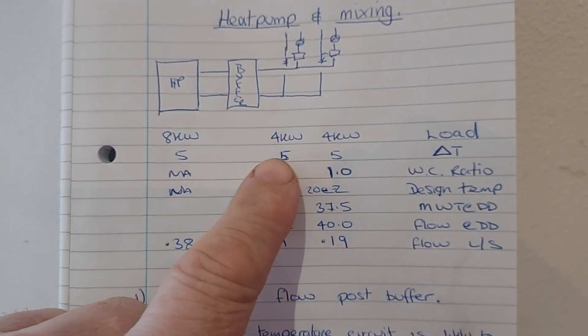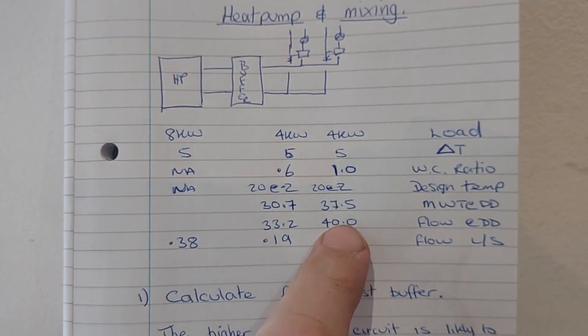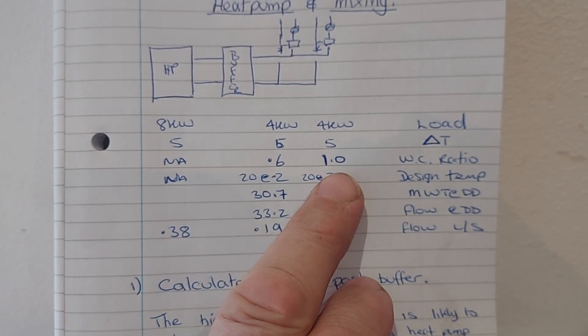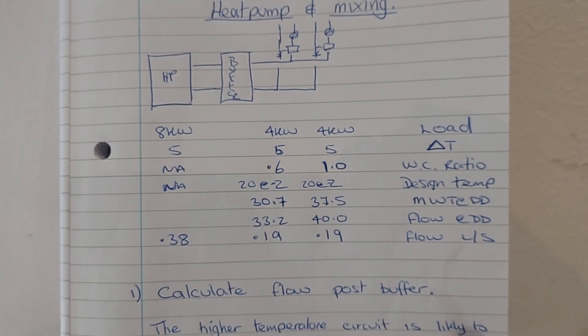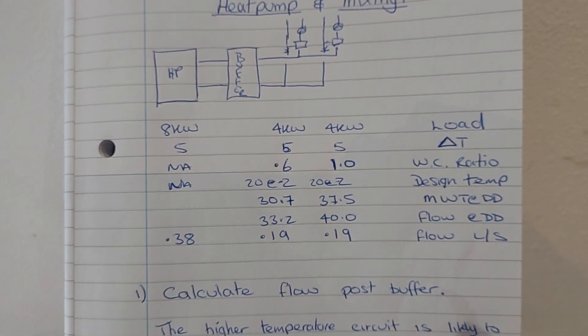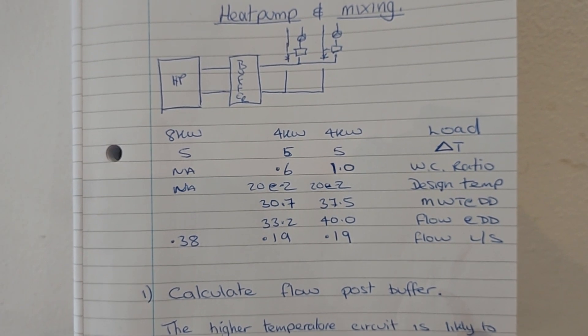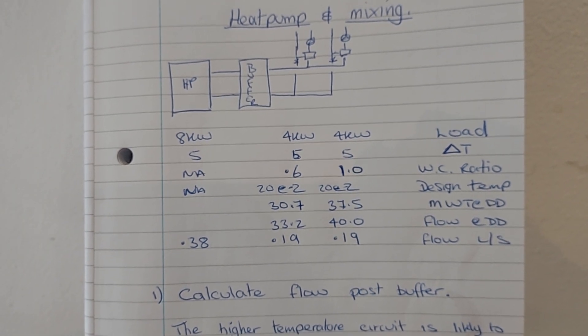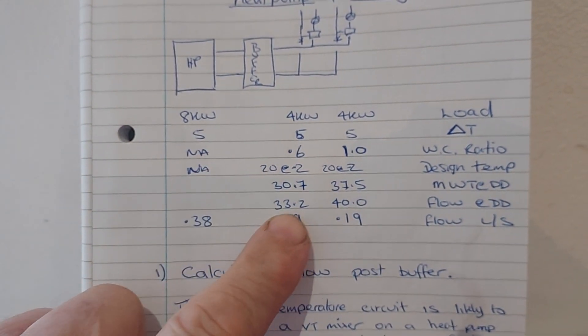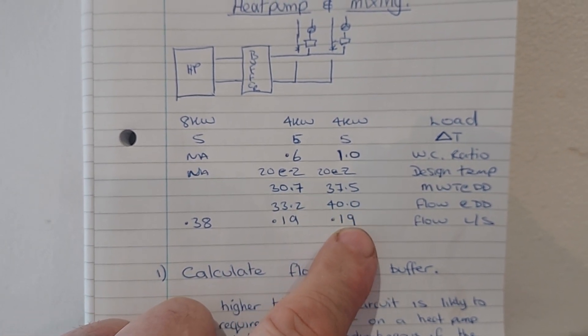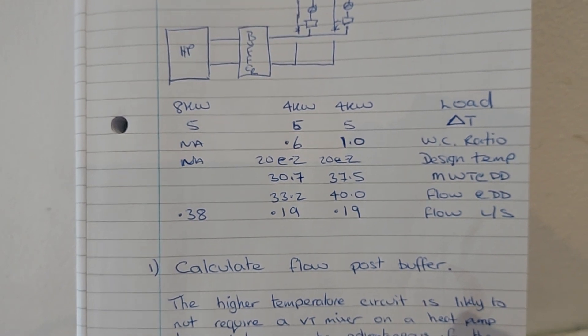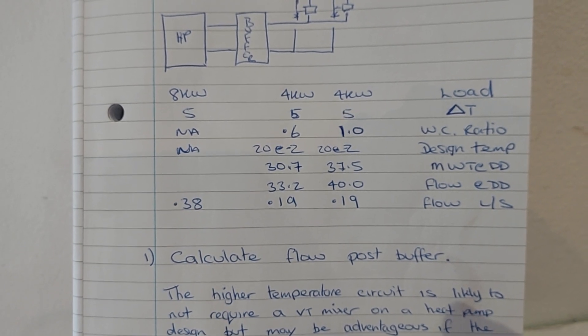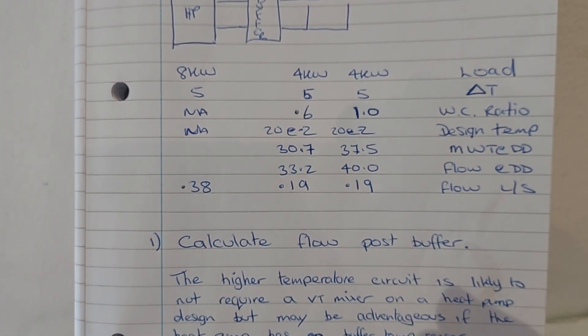Here we've assumed an 8kW system and we've got 4kW on both circuits. I've chosen a weather comp ratio of 0.6 and 1.0. I'll do a separate video on weather comp ratios, actually. I don't think I've done one yet. We've got a design temperature of 20 for the room, minus 2 for outside temperature, and that's going to give us a required flow temperature of 33 degrees and 40 degrees for our two circuits. The flow within those circuits for both circuits at 4kW and delta T5 is going to be 0.19 litres per second, and the flow rate for the heat pump is going to be 0.38.